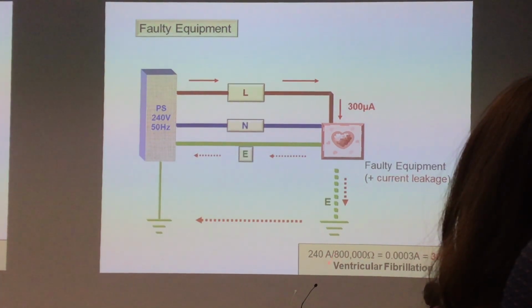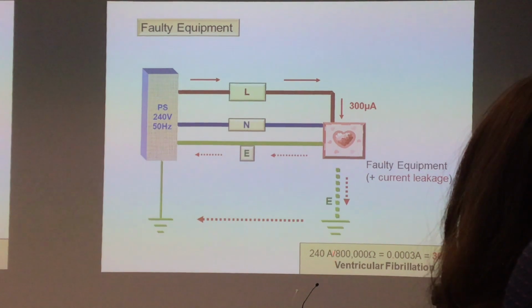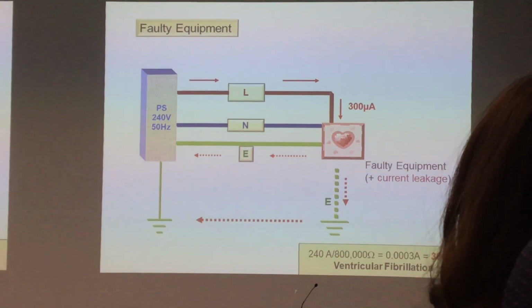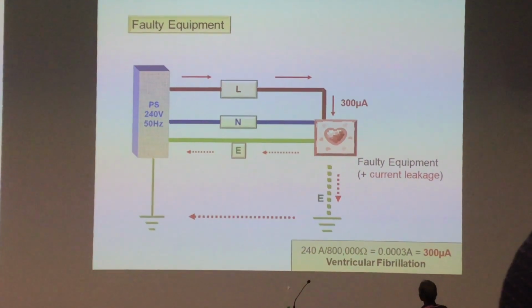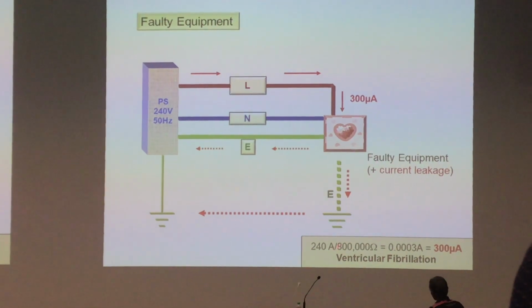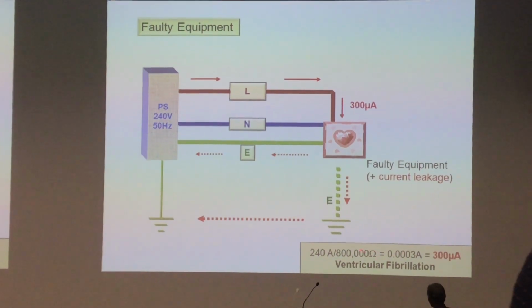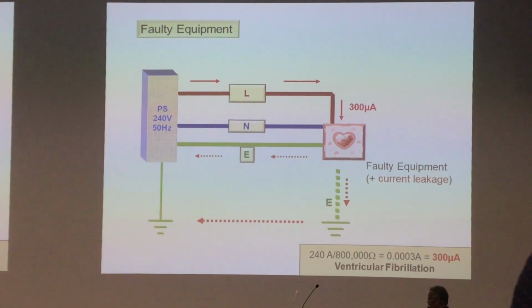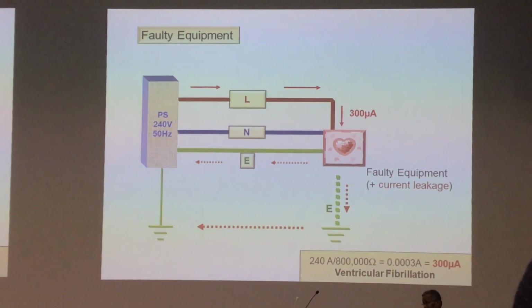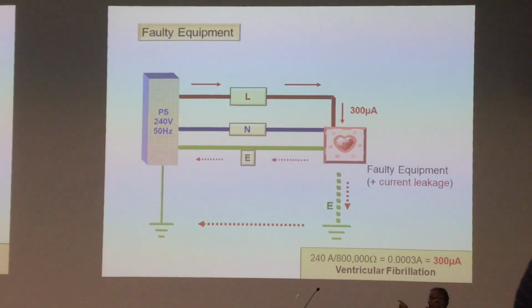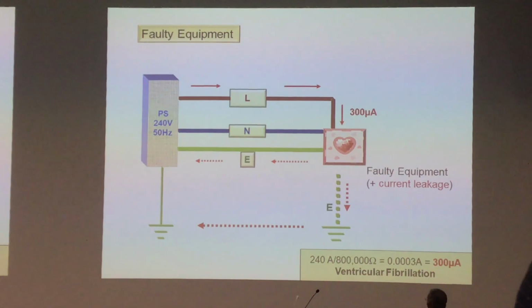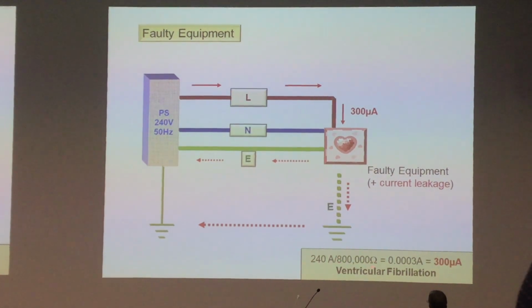So, example here. Say the voltage is 240 fixed, and the resistance is very high, but there's direct contact to the heart via the saline catheter or pacemaker cable. Even though the resistance is high, the amount of current to cause VF directly is very small, 300.